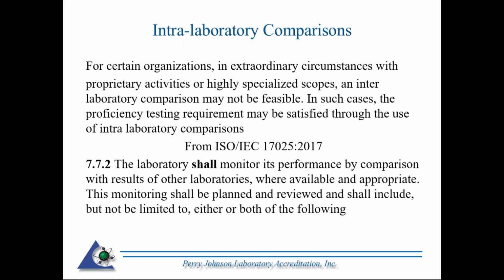And intralab comparison. So again, this is something that needs approval from PJLA headquarters. This would be an example of testing just within the walls of your organization. So, if you have, say, a lead technician, have them test or calibrate an artifact, test a sample, and then you have the other folks test behind them, and then you can compare the data in a meaningful way.